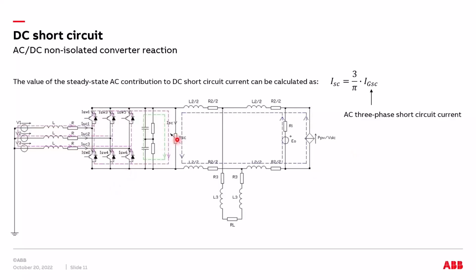If we have a short circuit on the DC side, imagine the worst case with a fault resistance negligible, practically equal to 0, apart from the resistance of the cable connection. As you can see, we can have a triple contribution. The first one is the blue dotted line contribution coming from the batteries installed on our vehicles and passing through the DC chargers, according to the internal architecture of the DC-DC converter, as we can see later on.